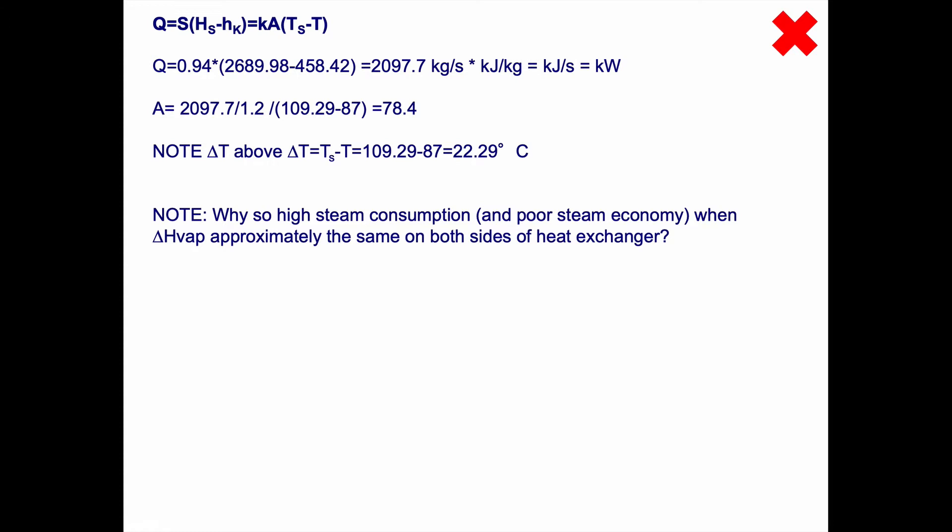Why do we have so high steam consumption and poor steam economy of 0.8, when the evaporation enthalpy is approximately the same on both sides of the heat exchanger? Shouldn't it be that the energy given away by the steam should be used for evaporation? And if the evaporation enthalpy is approximately the same on both sides, shouldn't the steam economy be 1? Well, it should if we had a preheated feed, but we don't. The feed only had 38 degrees Celsius, so it's not preheated enough. If we preheat it, we will get better steam economy.